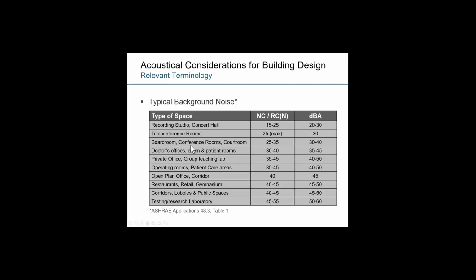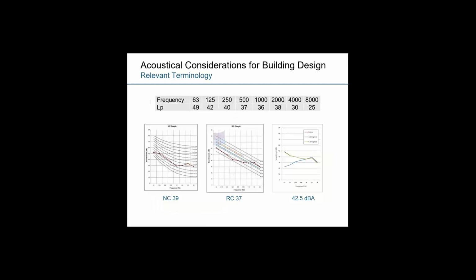Something like an office or a boardroom or a conference room would have a specific noise criteria, or NC, associated with it. If you're not familiar with these ratings, they're quite simple to understand, and I'll take a minute to describe what it is. In general, these single number references, NC, RC, dBA, are taking that individual octave band sound pressure level, and if you look at the table at the top, in 8 different frequency octave bands, you have a corresponding sound pressure: 49, 42, 40, and so on.